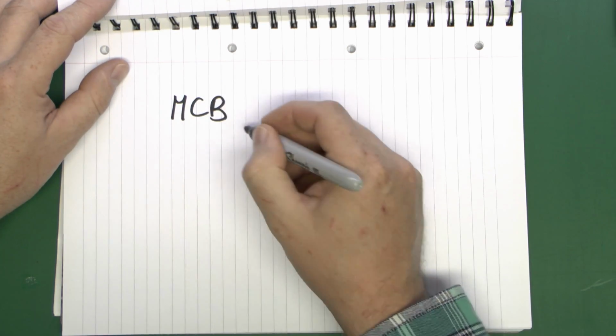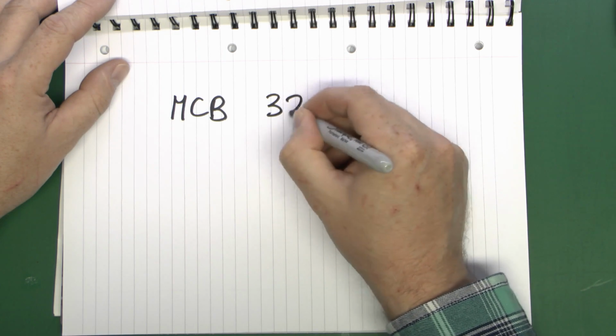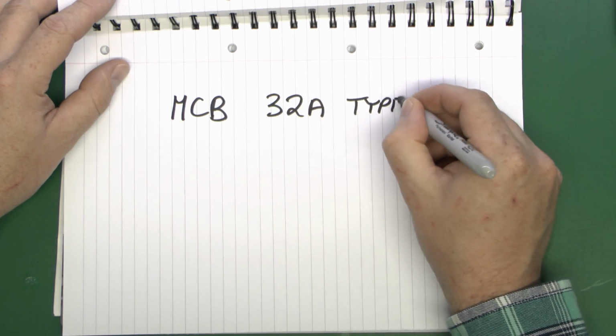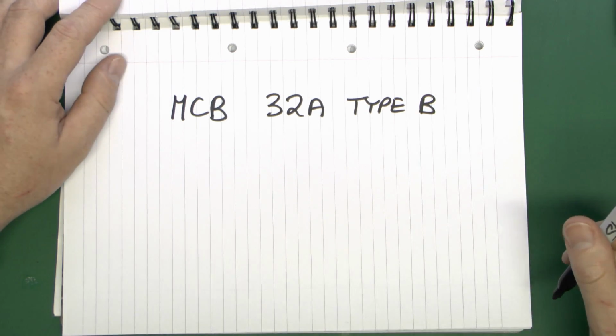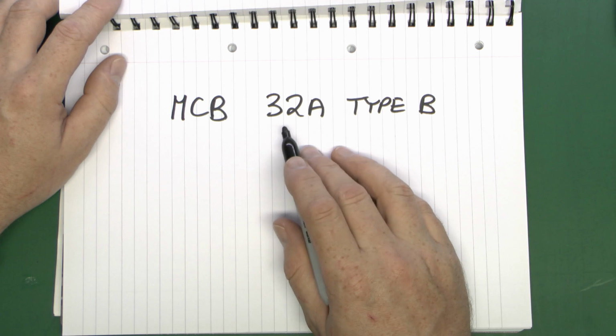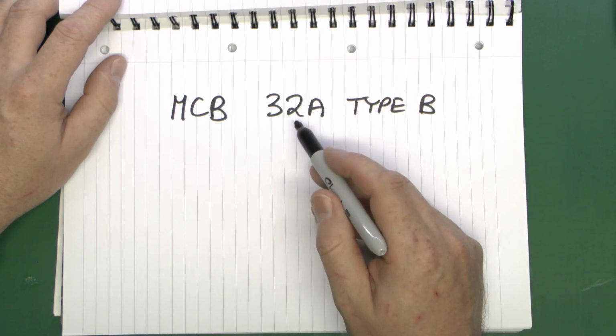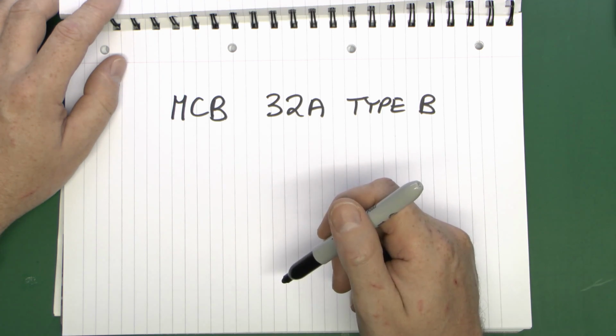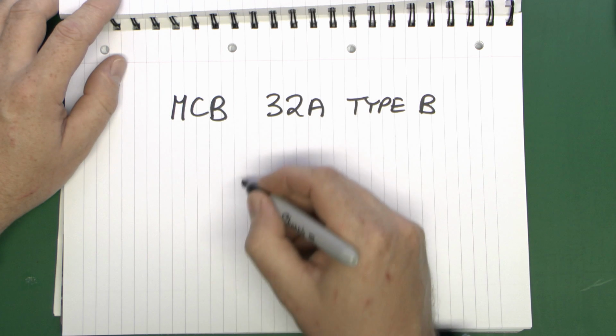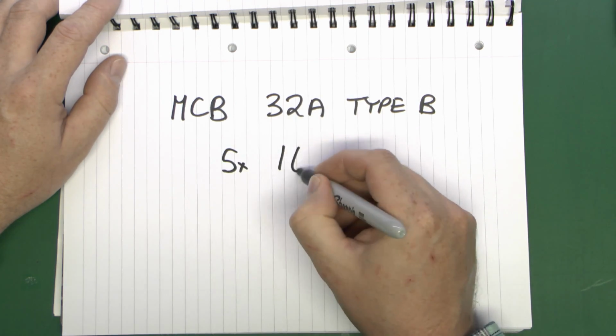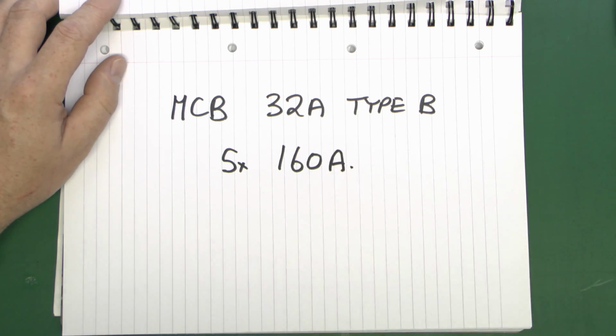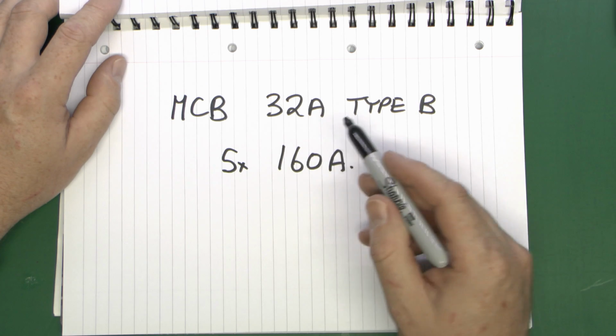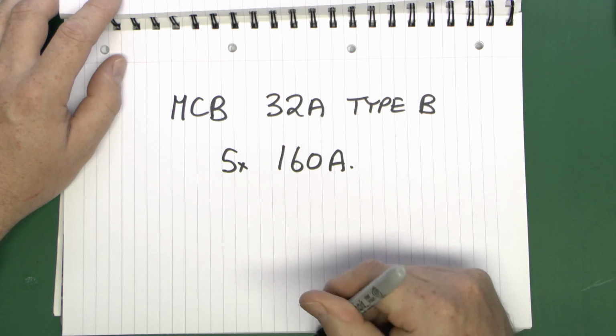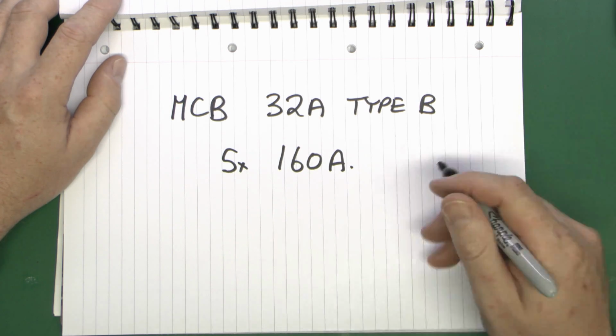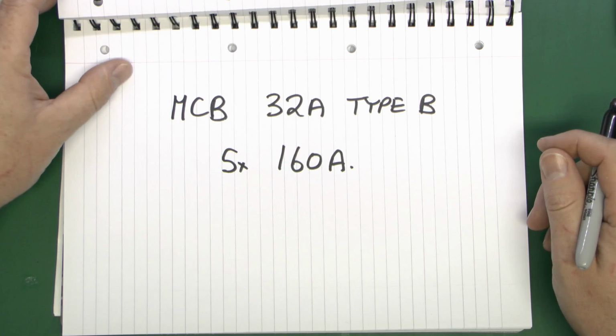Now, if we had a look on this page here, if we had a circuit breaker, or MCB as they're currently called, and say this was a 32 amp, and it was a type B, which again is by far the most common, then for this to reliably trip near instantaneously, we need a current to flow through this in the region of 5 times its rated current. So in the case of this particular one, that will be simply 5 times 32, which of course is 160. So if 160 amps is suddenly shoved through this circuit breaker, it's going to pretty much trip off instantaneously, disconnecting the fault and of course stopping the cables and things melting and setting on fire. And of course that's the whole point of having the thing there in the first place.